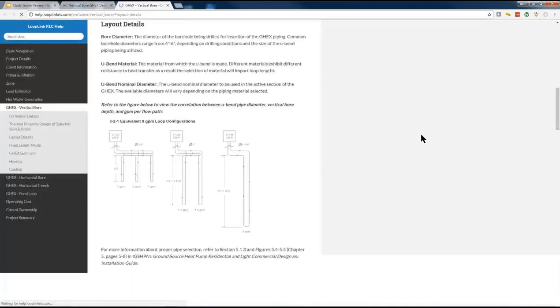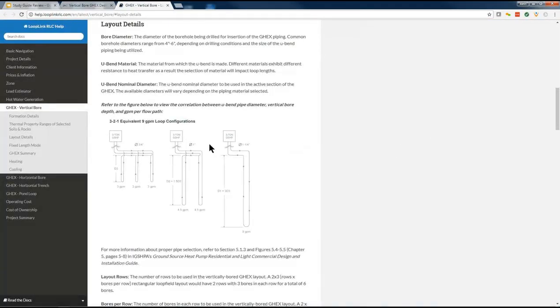And I'm sure you probably saw this image here. I just clicked on the help icon, but you probably saw this image in the RLC manual and throughout the IGSHPA PowerPoints. Basically, if you follow the rules of thumb shown on this drawing, you will have a layout that's guaranteed to have turbulent flow in the loop field without excessive head loss. Basically, with a 3/4 inch ground loop, you want to design your field for 1 loop per ton.